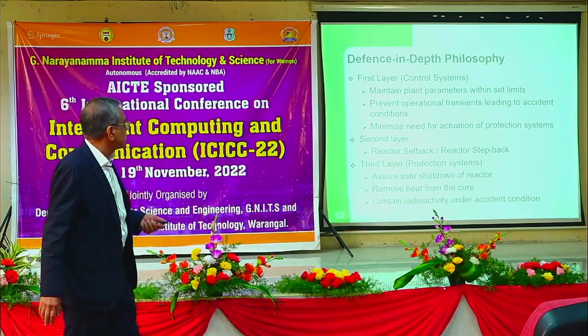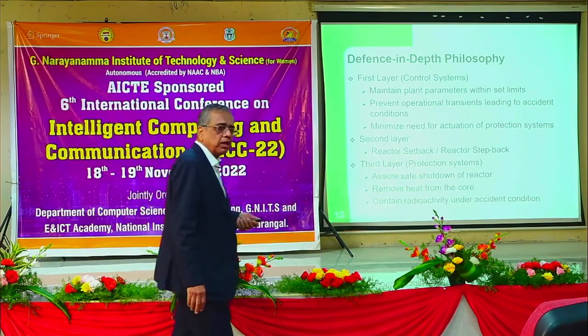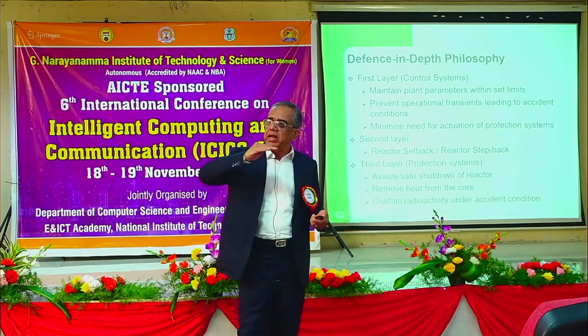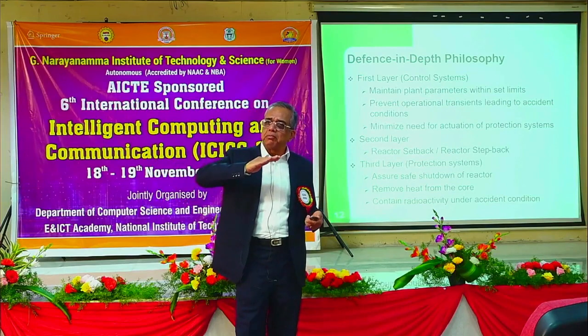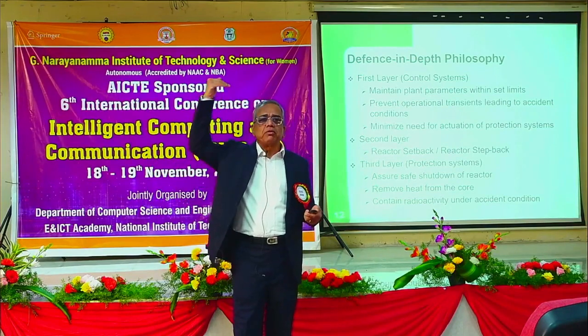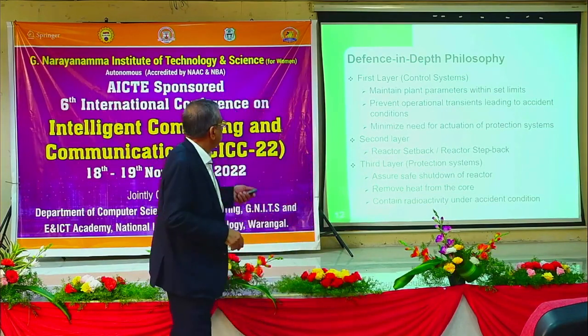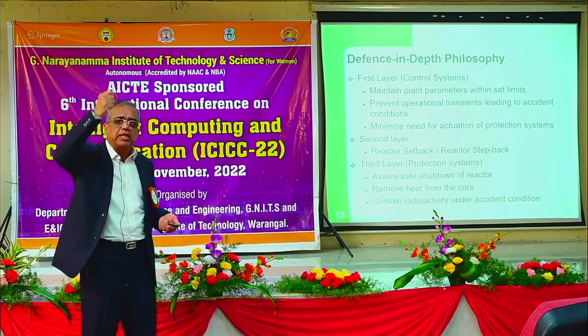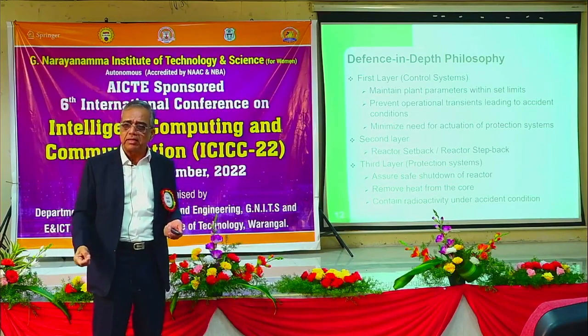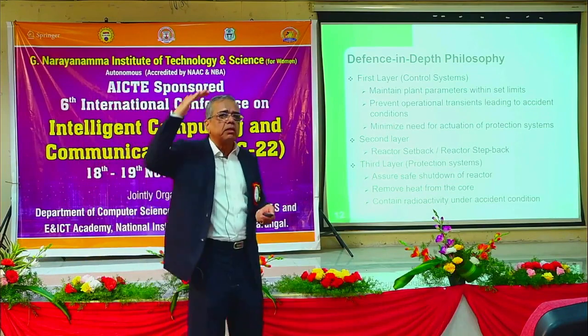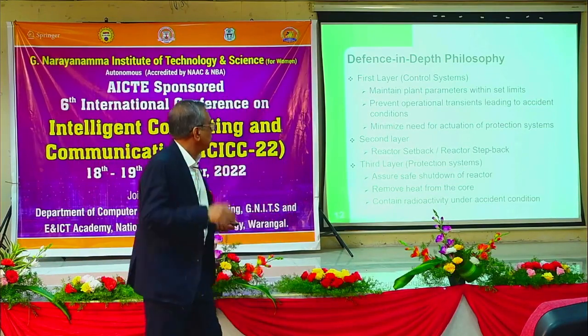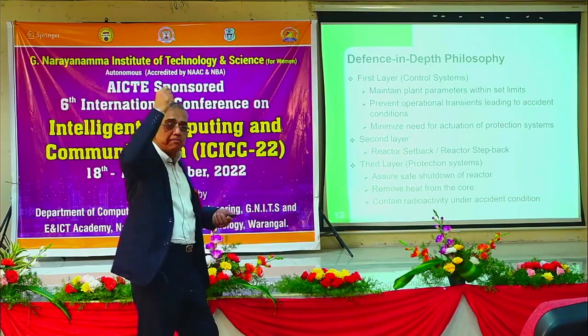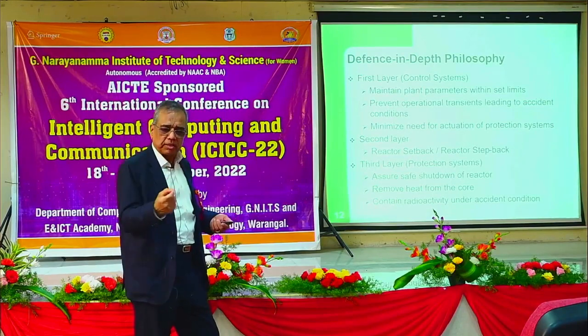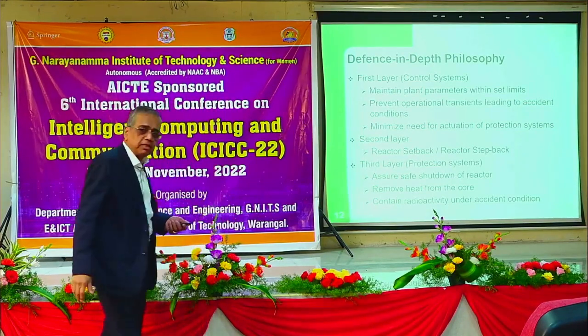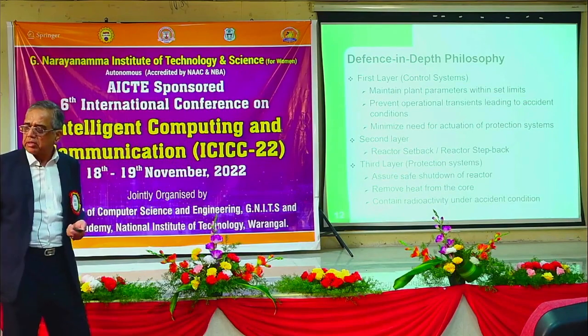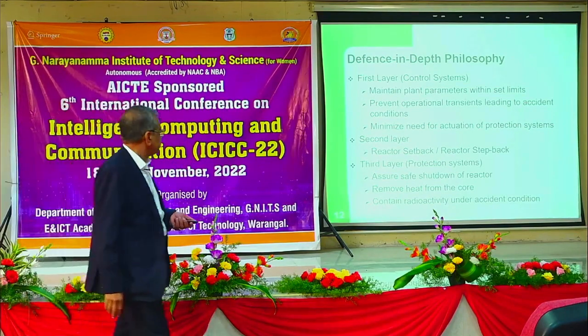Second layer is a reactor setback or reactor step back. What is that? Suppose some parameter the control system is trying to control goes beyond a certain limit, then you give a reactor setback, that is, reactor power is reduced at a certain rate till the parameter comes within limits. Or you give a step back, suddenly from 100% to 60% power, and then see whether the parameter comes back, otherwise finally shut down.